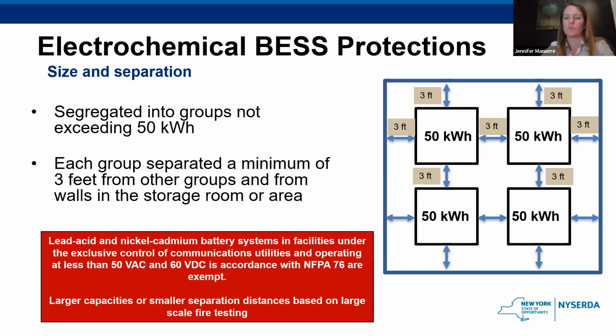You'll notice coming on this slide and coming up, we'll have some red boxes that are showing exceptions or possible exceptions to those requirements. The first one shown in that red box below is lead acid and nickel cadmium battery systems that are, I'm just going to read it this one time, in facilities under the exclusive control of communications utilities and operating at less than 50 volts and 60. If they're in accordance with NFPA 76, they are exempt. I couldn't tell you exactly why those particular systems are sort of grandfathered in like that, other than I know they've been using those batteries for many, many years.